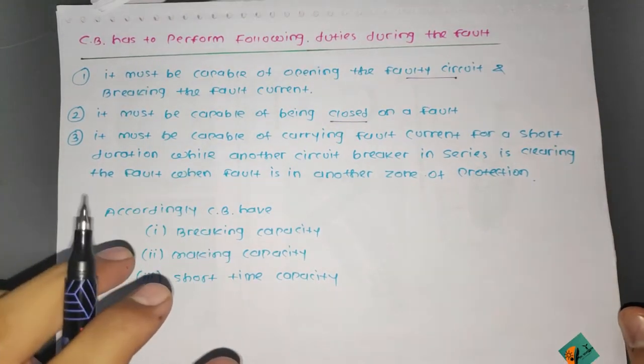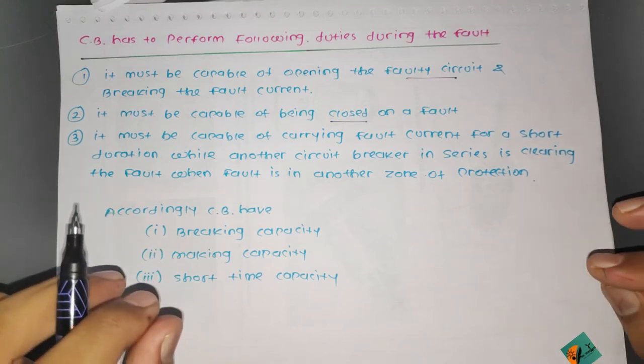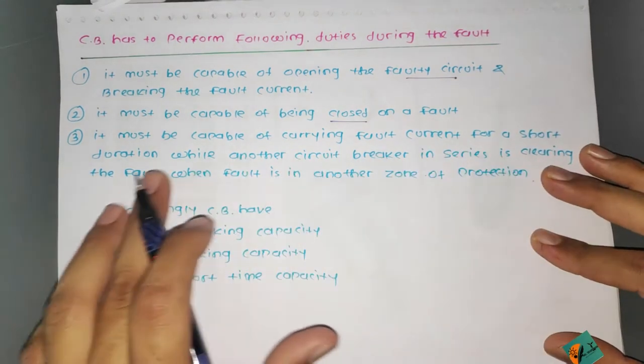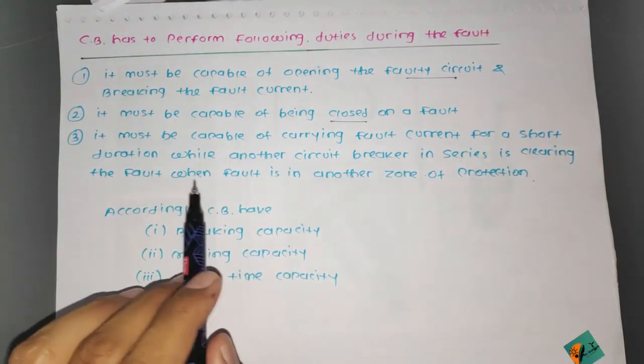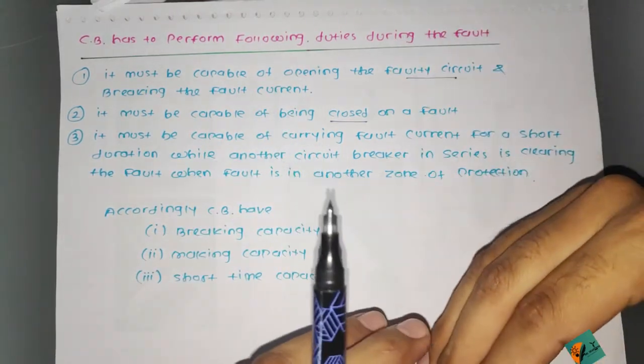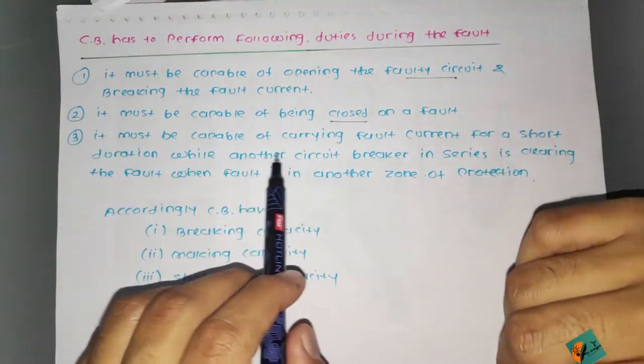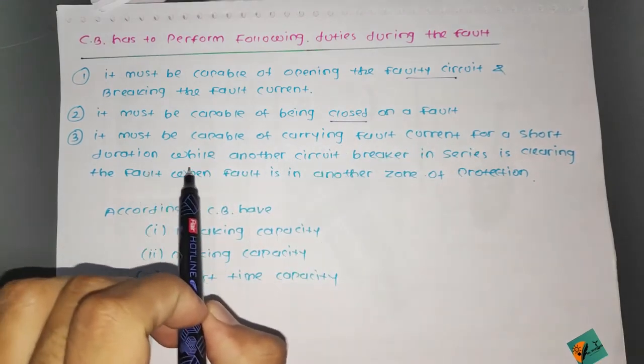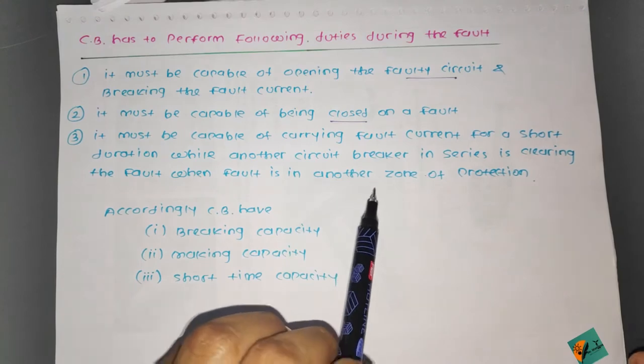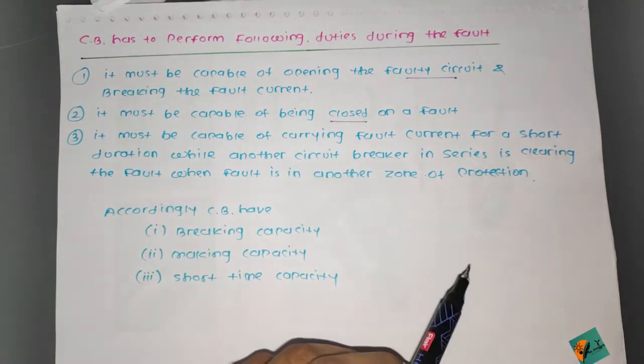Third, the circuit breaker must be capable of carrying fault current for a short duration while another circuit breaker in series is clearing the fault, when the fault is in another zone of protection. Zone-wise, the circuit breaker placed there must be capable of carrying fault current for a short duration while the other circuit breaker operates.